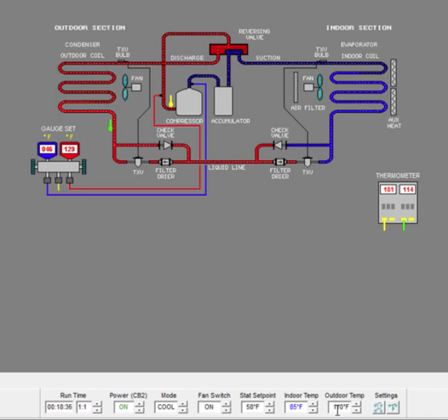Okay, but remember, we might be pulling more heat into the building as well. The outdoor air temperature will raise my condensing temperature and allow more heat into the building, so the system is going to have to work harder. But if everything's the same, we should still be maintaining that outdoor ambient difference. And 110 degrees is way over design conditions of a building. Okay, so let's pull this down a little bit. I'm just going to pull it down to 100 degrees, and we'll see what happens here.